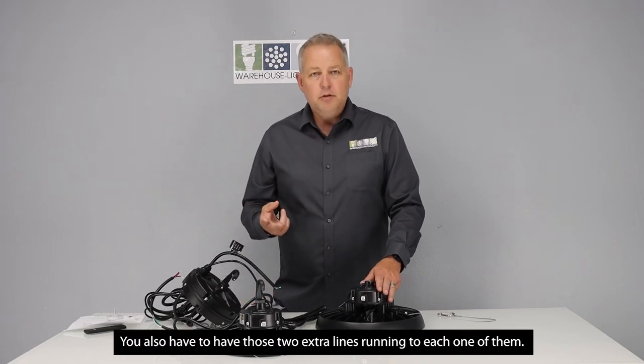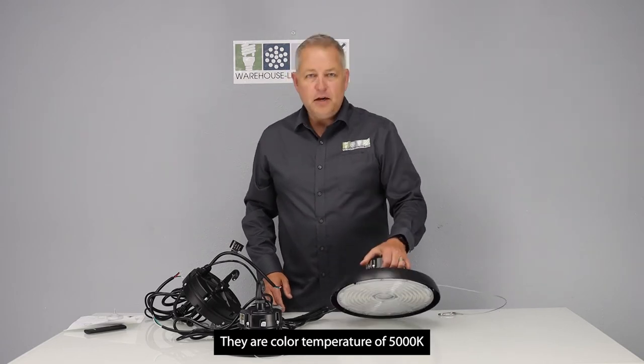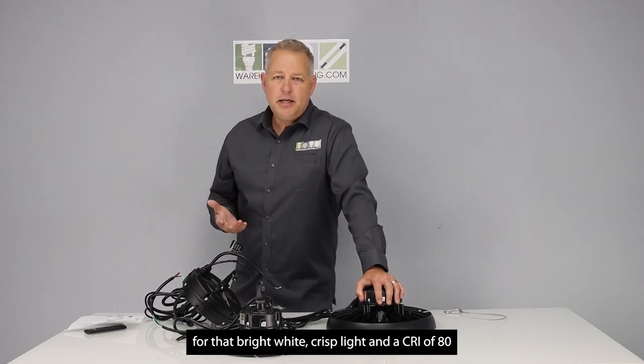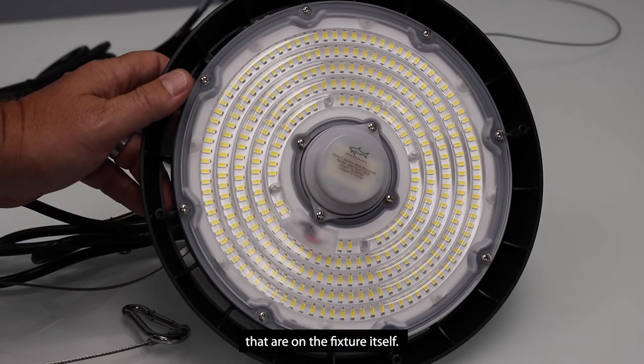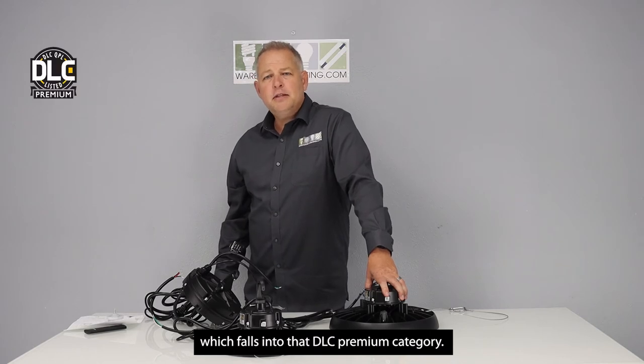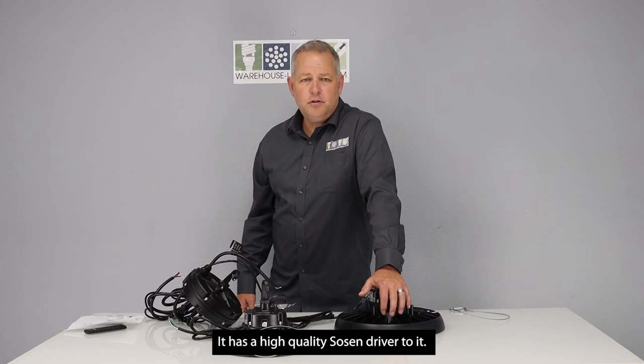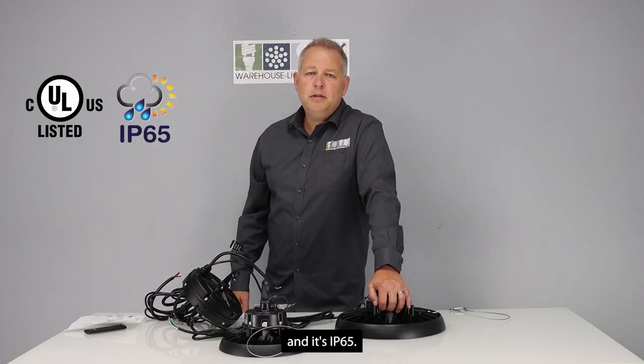You also have to have those two extra lines running to each one of them. They are color temperature of 5000K for that bright white crisp light, a CRI of 80, and roughly a beam spread of about 85%, which has to do with the optics on the fixture itself. The lumen efficiency is 135 lumens per watt, which falls into the DLC premium category. It has a high quality Sosen driver, is DLC CUL US certified for use in Canada and the US, and is IP65 rated.